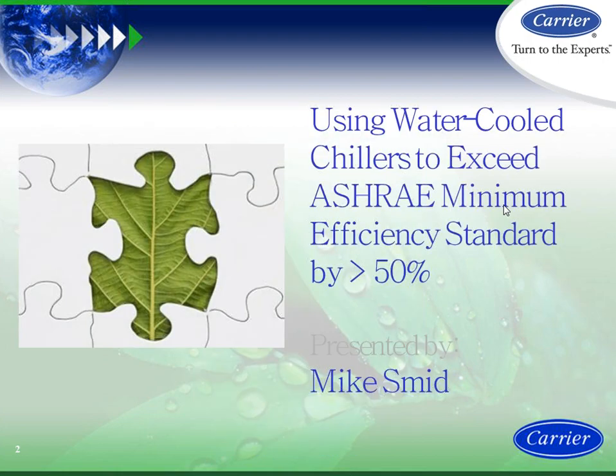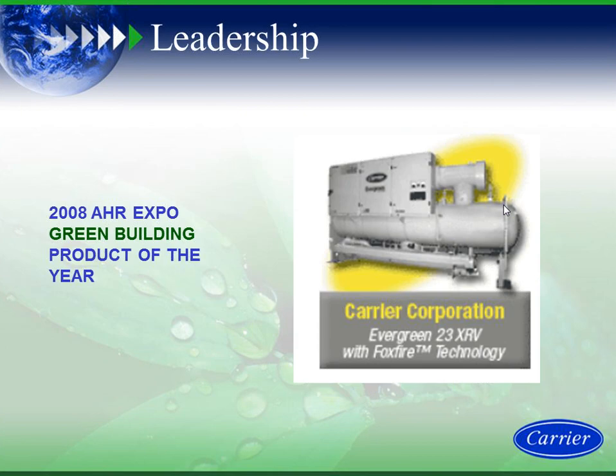So what we're going to do here is look at utilizing a Carrier water-cooled machine and exceeding the ASHRAE minimums by greater than 50%. The main core to the product, and the main reason why we can get to these 50% levels, is the 23XRV variable speed tri-rotor screw chiller, 2008 Green Building Product of the Year, from 250 to 550 tons. We're going to go into detail a little bit about this, but mainly what we're going to talk about is chilled water plants and optimizing them today.